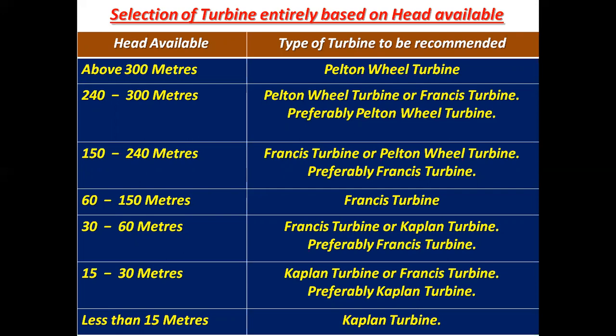150 to 240 meters, Francis turbine or Pelton wheel turbine, preferably Francis turbine. 60 to 150 meters, preferable turbine is Francis turbine. 30 to 60 meters, Francis turbine or Kaplan turbine, preferably Francis turbine. 15 to 30 meters, Kaplan turbine or Francis turbine, preferably Kaplan turbine. Less than 15 meters, Kaplan turbine.